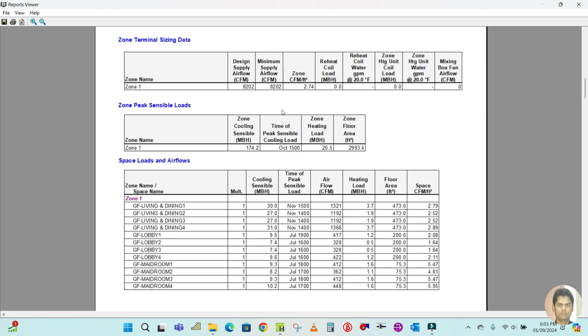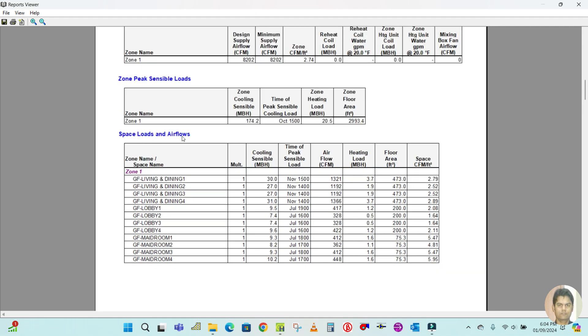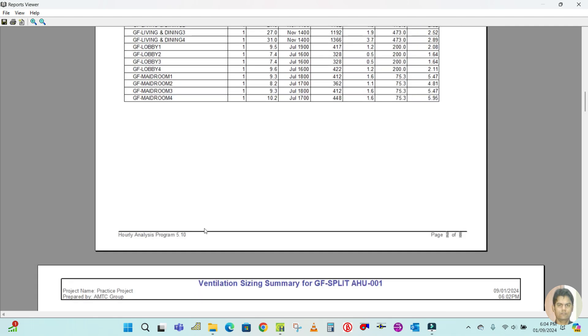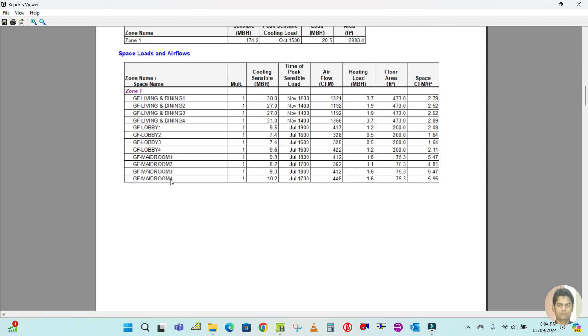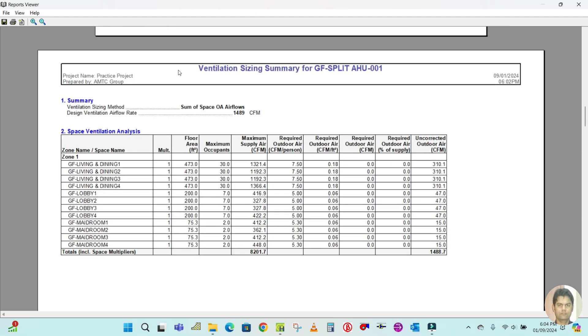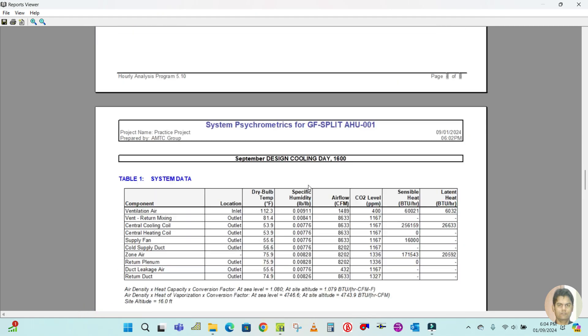The zone sizing summary shows Zone 1 details including space load and airflow. Each space that was added to Zone 1 is listed individually with its details. The ventilation sizing summary shows the fresh air requirement for each space. This process is similar to the package unit — you mainly just need to change the air system name.